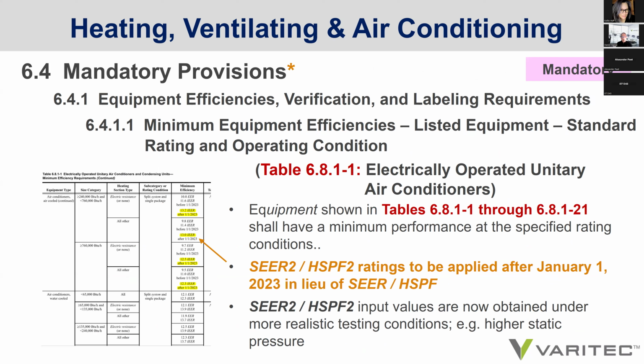Mandatory provisions. Let's look at equipment efficiencies. All of these are mandatory under the standard. So look at table 6.8.1-1. We'll just show you quickly the reference to the IEER table that these standards are going to have to be adjusted to comply with SEER 2 and HSPF2 ratings as opposed to SEER ratings and HSPF, so for heating performance. So these input values are now under a more realistic testing condition design in order to make sure that their values more closely represent actual installations.